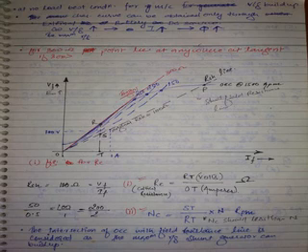Why? Because if you observe, the curve comes down. If it drops down, automatically there is no build up. That's why this is the critical. So automatically, ST represents the critical speed. So RT by OT, V by I, gives you the critical resistance, and from this, ST by RT times that N, you will get NC.